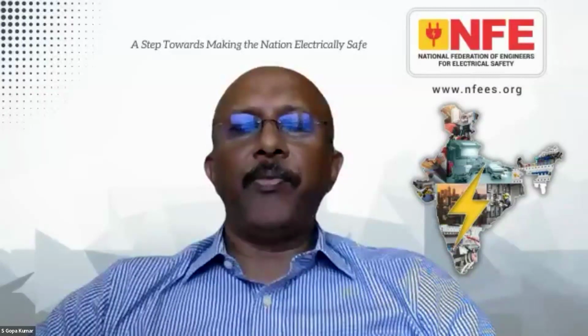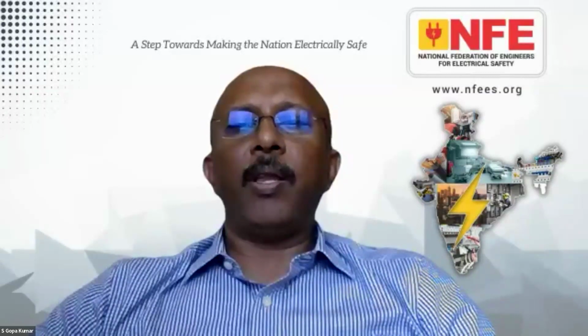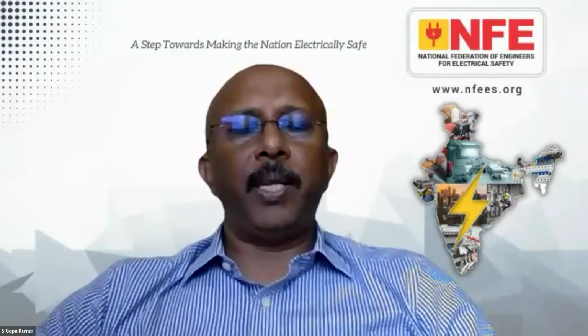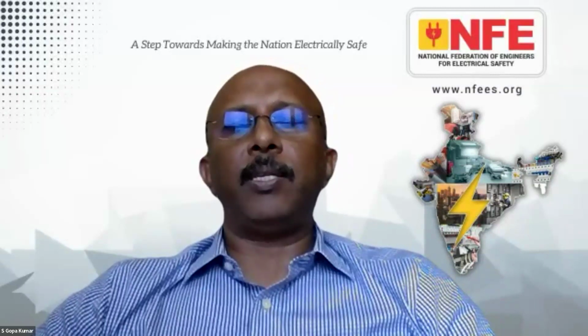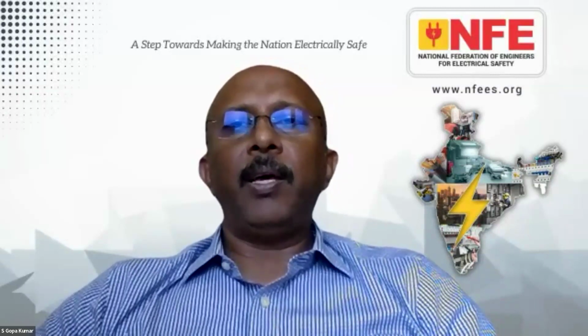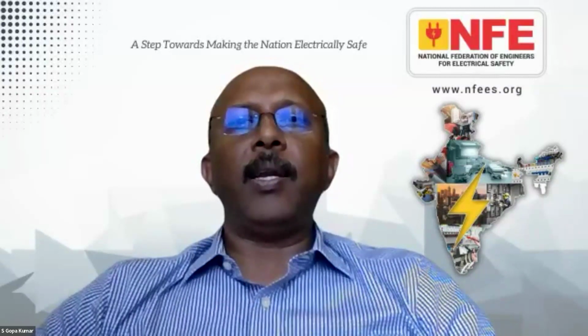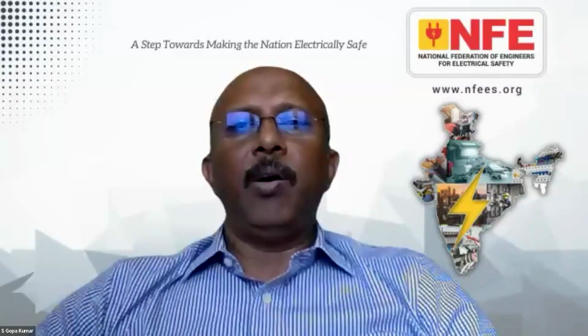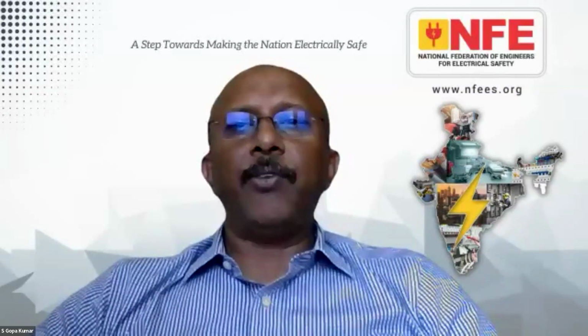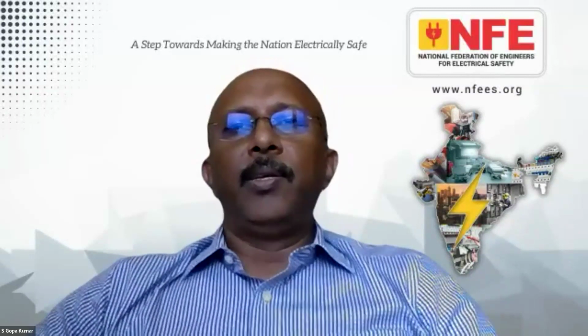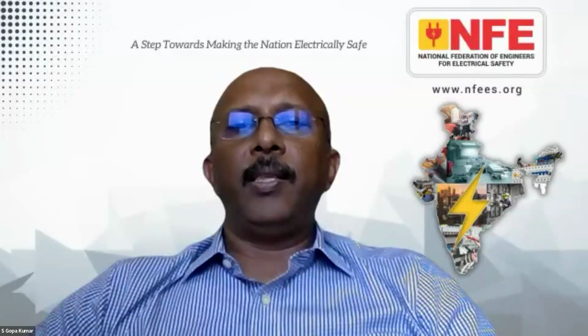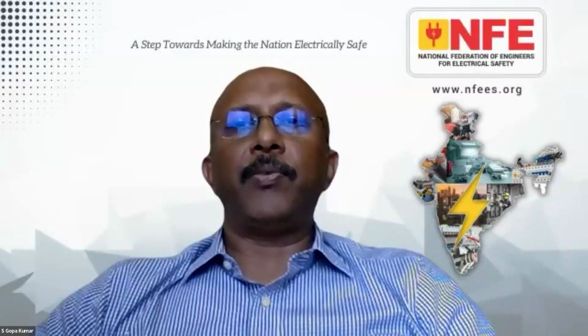Okay, so both are two different products. The Megger, or the insulation tester, is basically used to check the insulation resistance between the earth and the current carrying conductors, or between the current carrying conductors if there is no load connected. And this one is testing the impedance of the entire circuit.